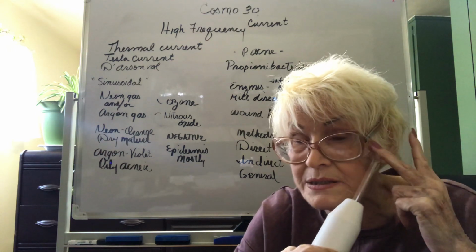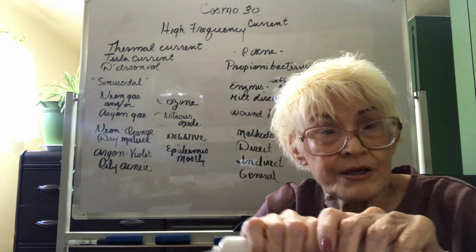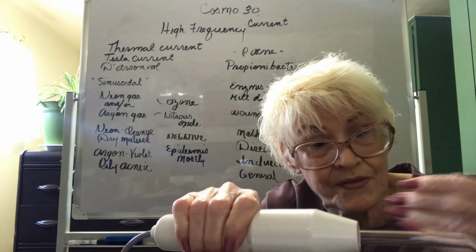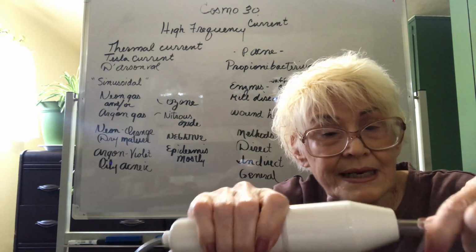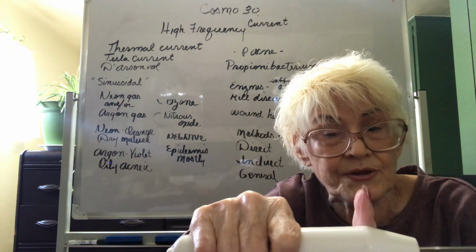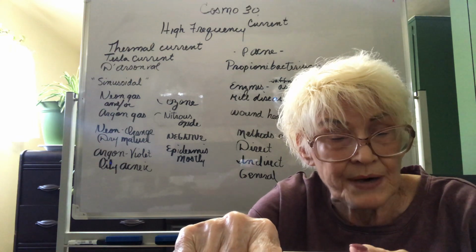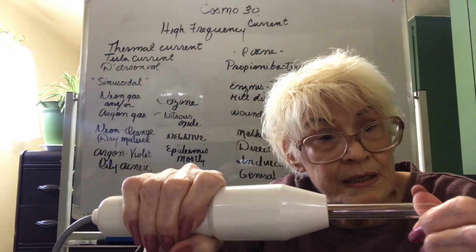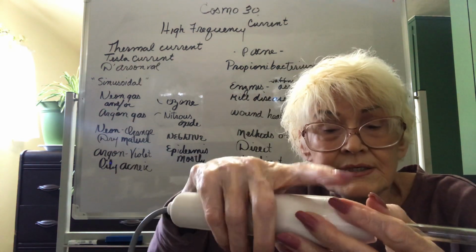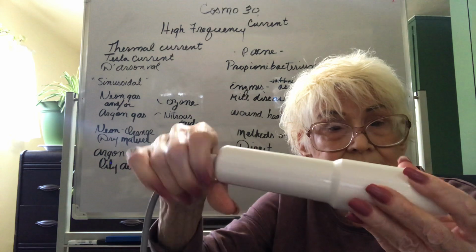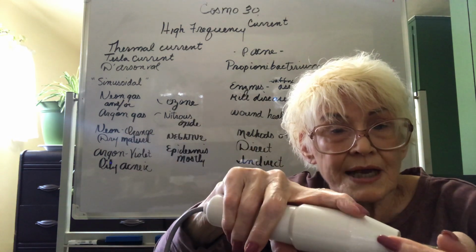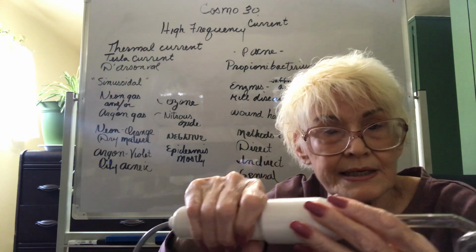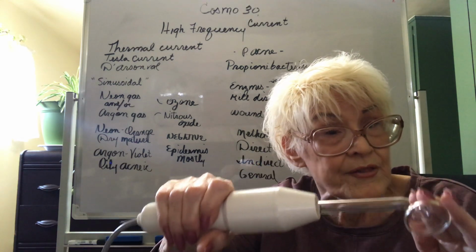If you need to, you can remove it, or you can leave your finger there to prevent it from bumping around. But what you need to understand is because this is where the coils are, this gets hot on the inside. As soon as my metal electrode makes contact with these coils, this area right here produces a lot of current, not the same amount that comes out here. So I need to be sure that I'm holding it back here. I'm not doing this, and I'm definitely not doing this. Okay, I'm gonna hold it back here, making contact out here with my other hand.